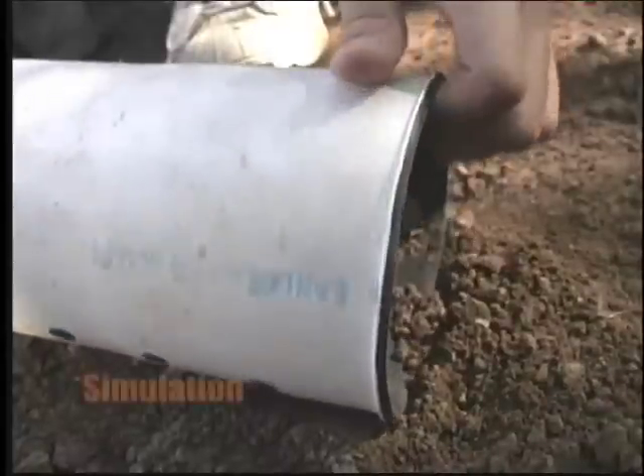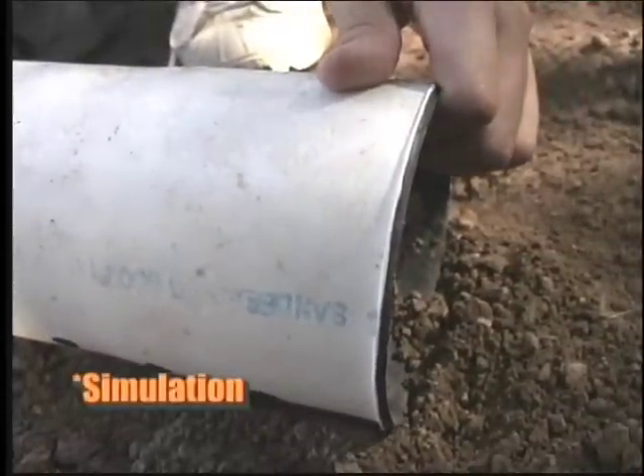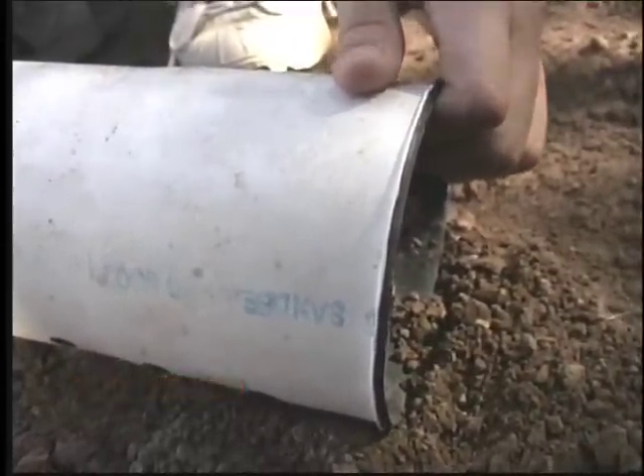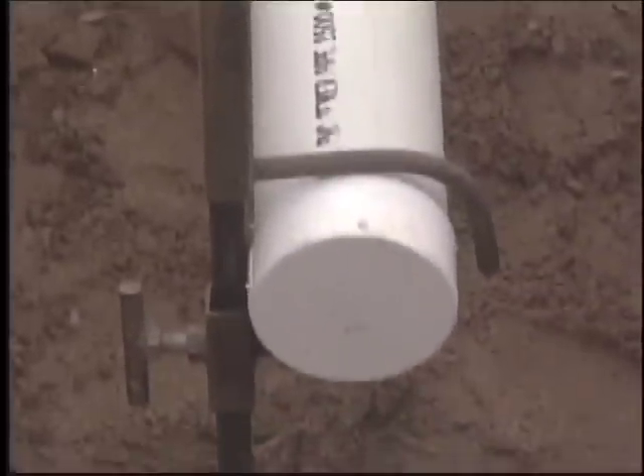During the assembly of the plastic piping in the trenches, it is important to ensure that the perforations are not at the bottom of the pipe. Ensure outlet holes are at 4 and 8 o'clock positions, and do not point straight down. Place caps at the end of the pipes if they are not connected.